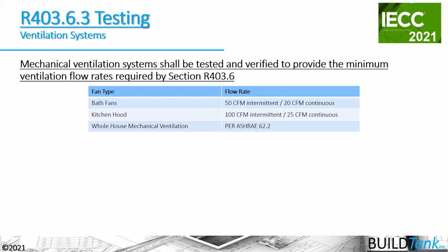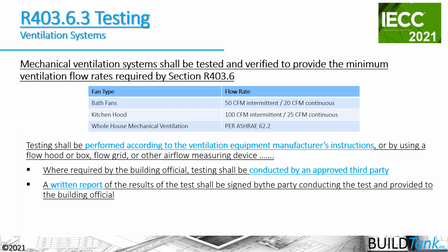What we're seeing, because the Energy Star program requires this type of measurement, is that a lot of times installation of these fans diminishes its ability to push air. What we do know is that the typical builder grade bathroom fan that pushes 50 CFM doesn't push 50 CFM anymore when you attach duct work to it, and especially if that duct work is tortuous, meaning that it has a lot of bends and elbows in it. So what it will mean probably is that most of these bath fans will have to be upgraded to a better fan that pushes a little bit more air, and that duct installation needs to be substantially better.